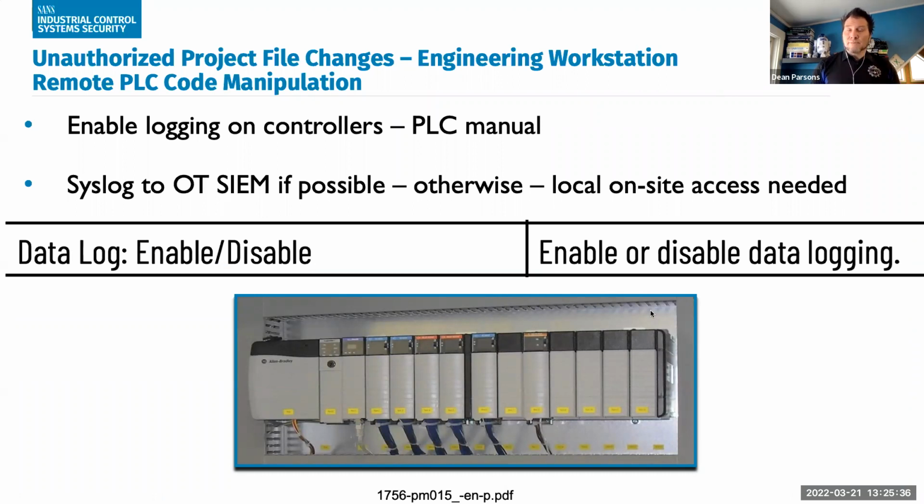So this is directly from one of the manuals for the PLC for this specific vendor. It literally is, you can change this aspect while setting up the controller, or even after the fact as well. And I do want to point out again that some of these devices, even though they may be a legacy in your environment, may have the ability to upgrade the firmware to enable syslog to an OT SIEM or some other aspect for logging and correlation.